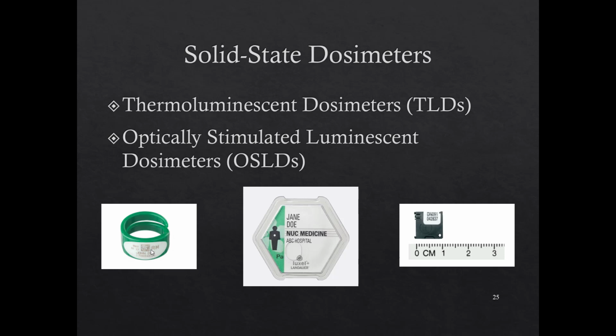After they're calibrated towards a known standard, so after you perform a calibration in-house, which your physicist will do, then you can use these to assess patient dose, which is great. Good for pacemakers, good for checking the dose under a bolus, or if you want to make sure that the skin's getting adequate dose, you can also put that right on the patient and then just process it and know that the plan is sound.